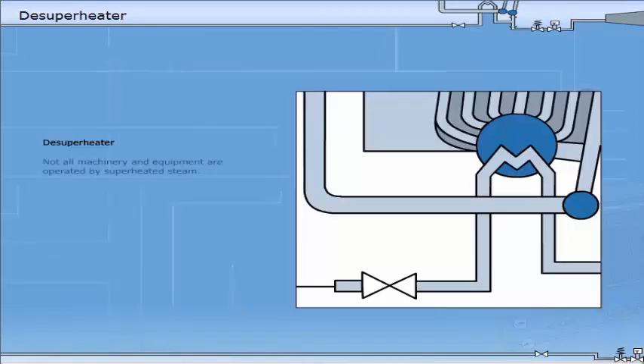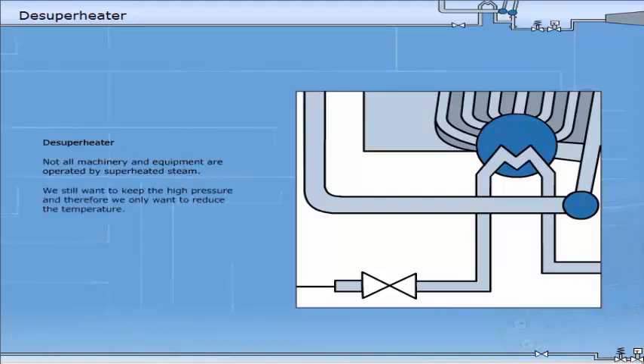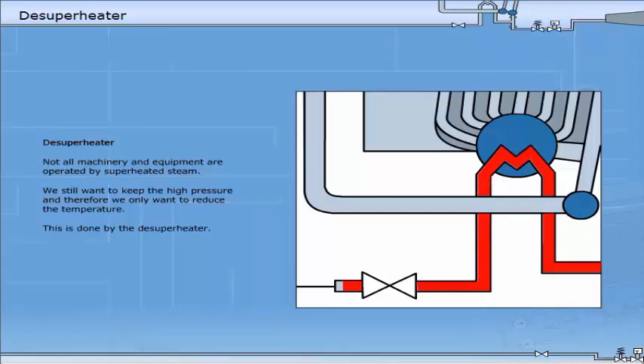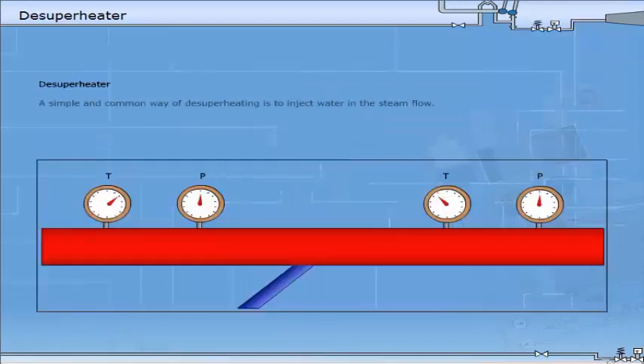Not all machinery and equipment are operated by superheated steam. We still want to keep the high pressure and therefore we only want to reduce the temperature. This is done by a de-superheater. A simple and common way of de-superheating is to inject water in the steam flow.